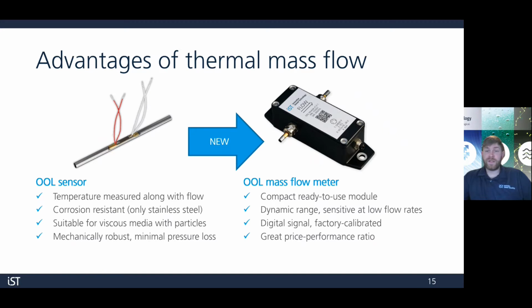There are several different ways to measure liquid flow, so here I'll highlight a few advantages of using a thermal mass flow measurement scheme. On the left, we have the OOL sensor, which we've been making for many years, along with evaluation electronics. This consists of two thin film chips on ceramic substrates, a PT1000 temperature sensor, and a lower resistance heater. The chips have a metallized backside and they're soldered directly to the stainless tube. This gives us optimal thermal coupling and the fast response time.